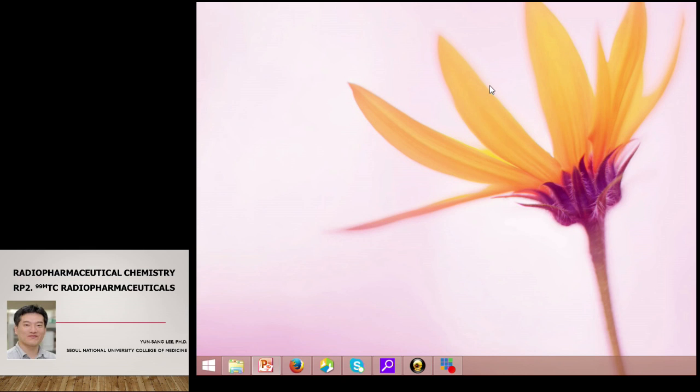So technetium-99m HMPAO is rare compared with technetium-99 HMPAO, which makes things worse. And if injected, the brain is not visualized, and only the soft tissues are there. So the technologists still come on Saturday and Sunday, and they just elute and discard, elute and discard, so that the ratio of technetium-99m over technetium-99 is maintained the same as during the weekday.